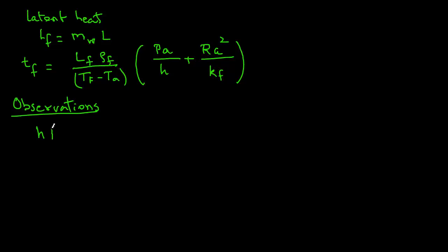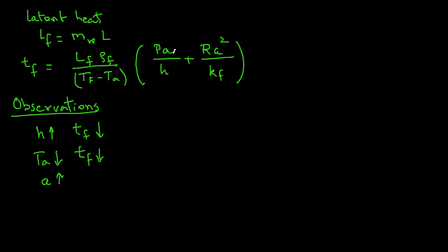We can make some observations from this equation. If the convective heat transfer coefficient H increases, then the freezing time will decrease — in other words, if we use forced convection during freezing, the time for freezing will decrease. Similarly, if we decrease the surrounding temperature Ta, then the freezing time will decrease, which makes sense: if our freezing air temperature is lowered, we will be able to freeze faster. Also, if the value of A — the thickness of the slab — increases, then the freezing time will also increase. Note that since we have A², the impact of a change in thickness is very profound; a slight increase in the size of the product can result in significantly longer freezing periods.